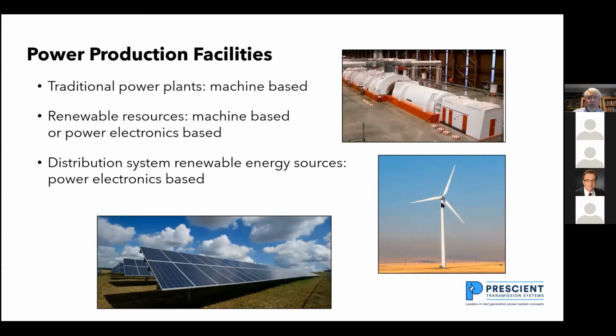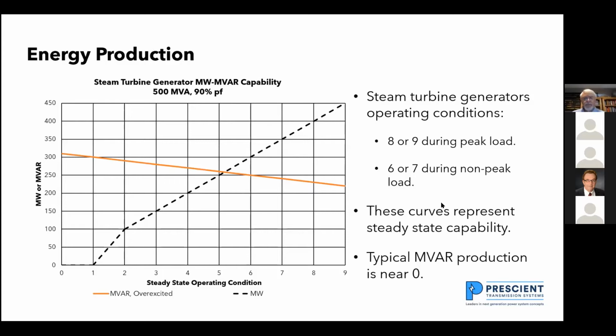So what we have to do is make sure we've got all our power electronics-based power production facilities in all our models. When I'm looking at things like this, if I look at how I produce energy, this graph shows the energy production capability of a steam turbine generator. Megawatts are the dashed lines. MVAR is the solid line. And on any given day, I'm operating at a certain operating point. Under a peak load condition, I may be operating this 500 MVA unit at 400 megawatts.